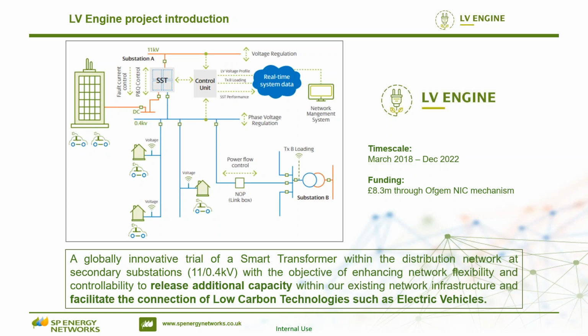So what we're going to do with LVEngine? LVEngine is basically targeting the application of power electronics within secondary substations. So we're going to design and trial a solid-state transformer within a secondary substation. And with that, we're going to bring some flexibility and controllability in secondary substations. That includes controlling voltage per phase separately on the LV bar basically, and we are planning to use smart meter data to inform this voltage control activity. We are planning to do power factor correction and cancel the imbalance load we see from the LV network, so HV doesn't see any imbalance load, and also provide power flow control at the substation, which can help us by closing the interconnection between two neighboring substations, sharing capacity between them.